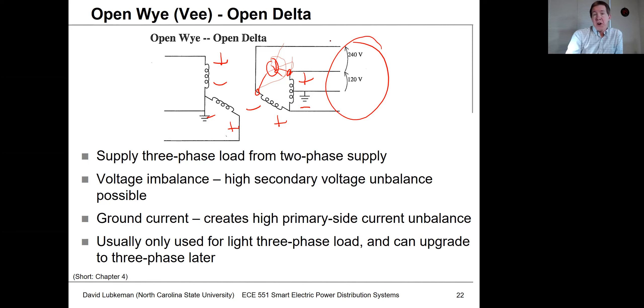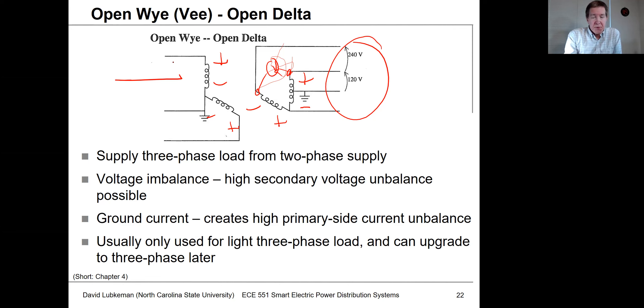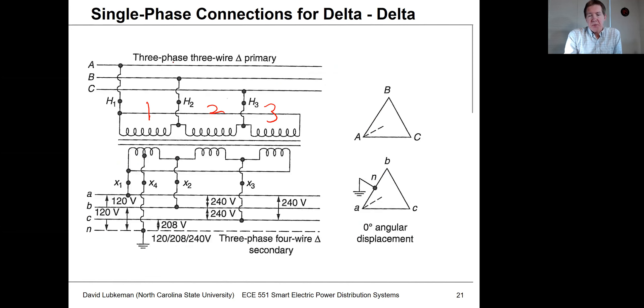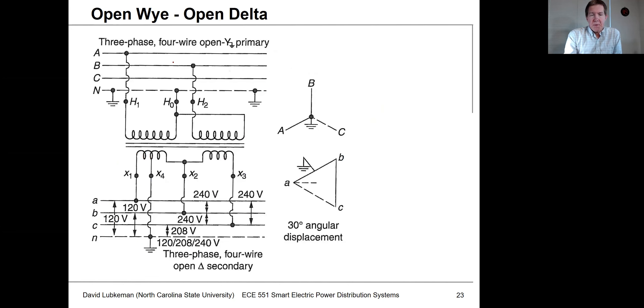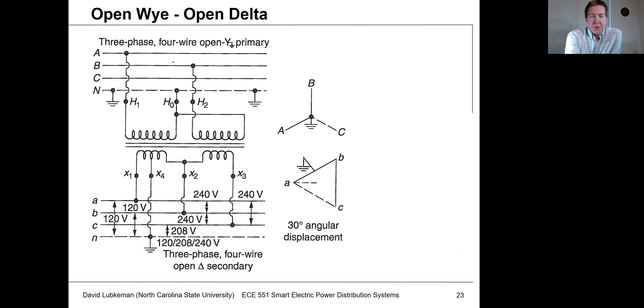You could start out with this two-transformer arrangement and upgrade to three-phase later by adding another phase wire and a third transformer. Here's what this actually looks like using the special-purpose two-transformer connection — it shows how to make all the necessary connections to get a three-phase voltage set even without the actual third transformer in the circuit.